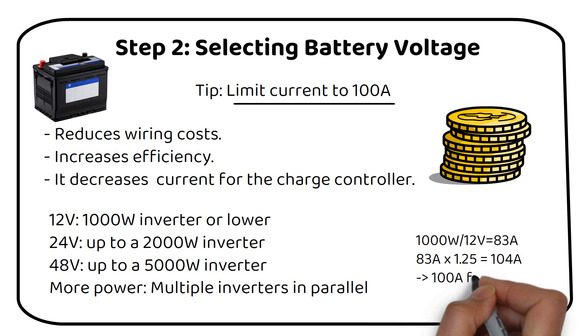To ensure safety, we apply a factor of 1.25 or 125%, which brings us up to 104 amps. Therefore, a 100 amp fuse would be appropriate for this inverter. However, let's not get sidetracked and focus back on the main topic.